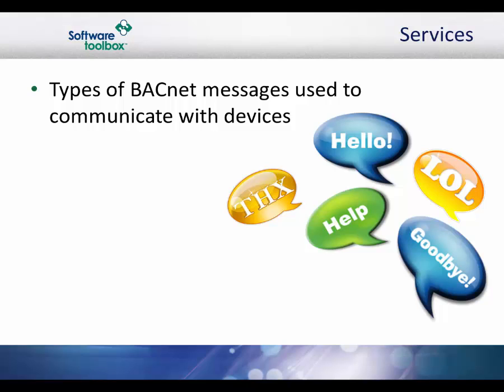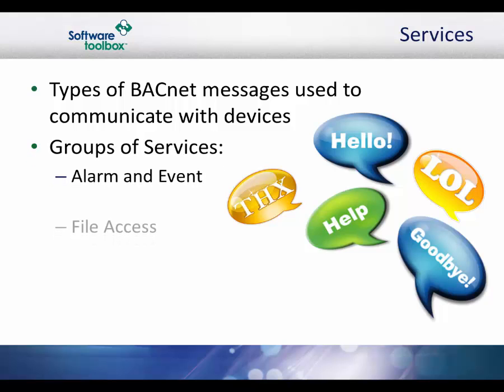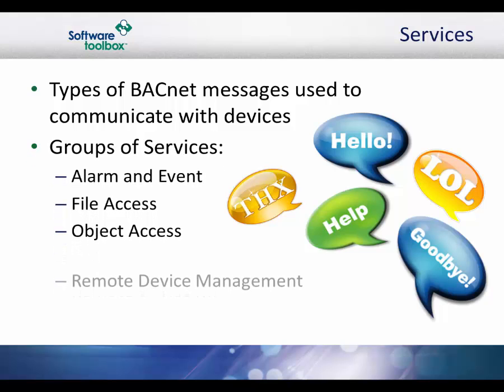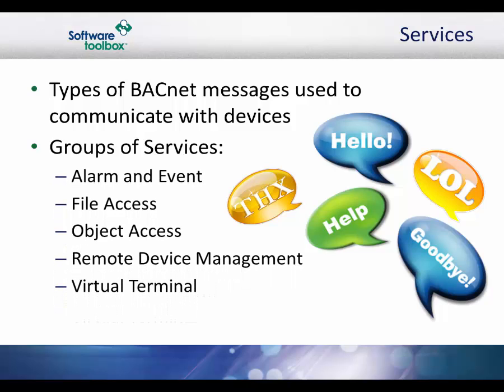There are currently five groups of BACnet message types. For example, one class contains messages for accessing and manipulating the properties of objects. A common one is the read property service request. This message causes the server machine to locate the requested property of the requested object and send its value back to the client. Other classes of services deal with alarms and events, file uploading and downloading, managing the operation of remote devices, and virtual terminal functions. Here are some examples of services categorized by their class.